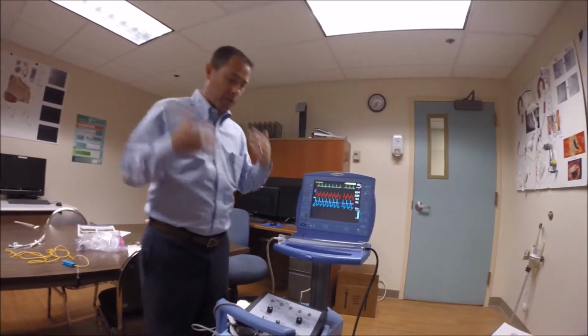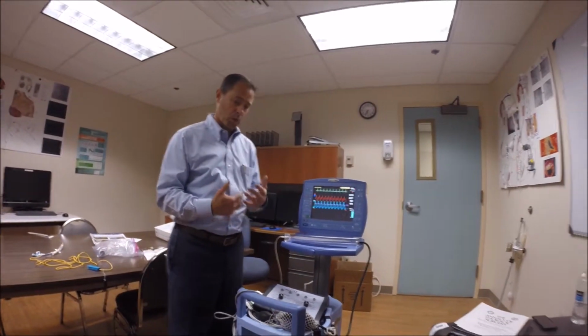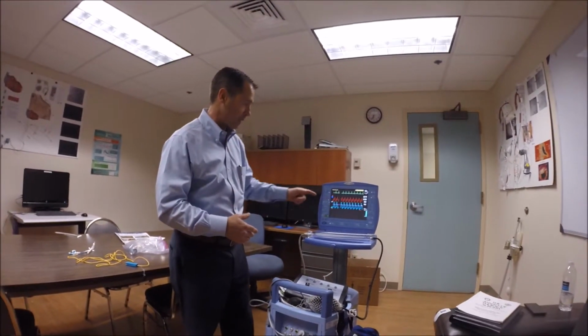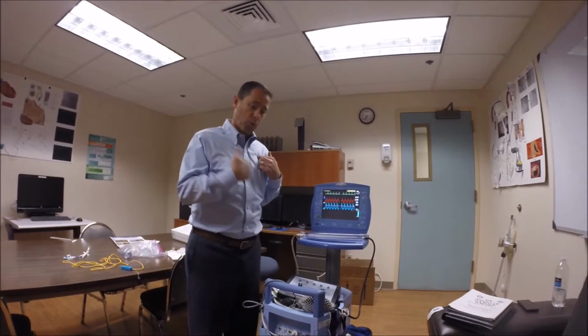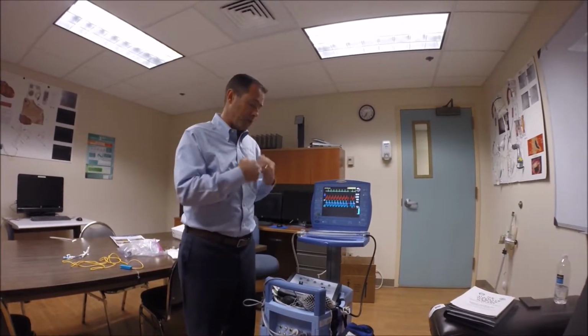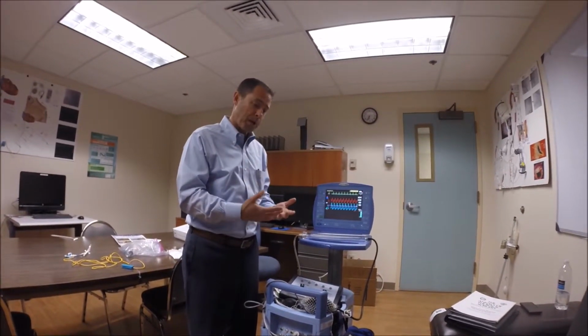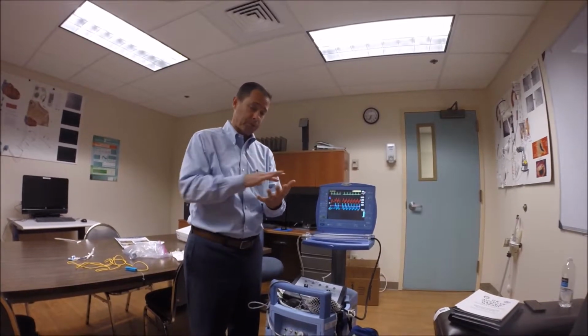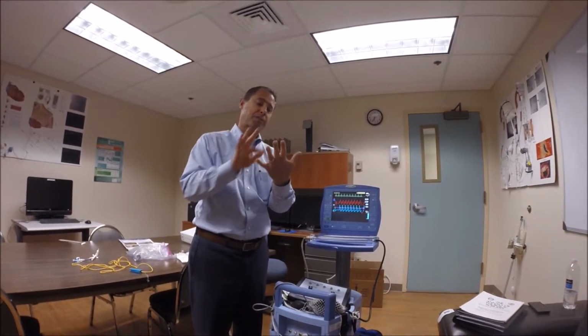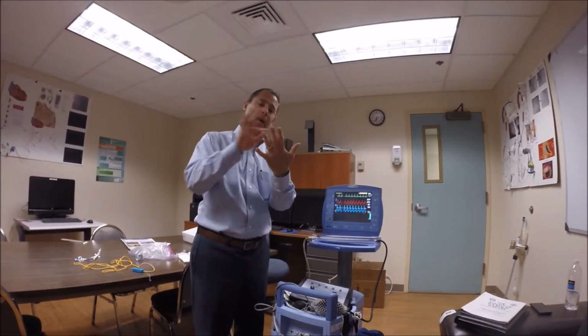In the background of the pump there's best signal analysis, meaning it's always capturing the right ECG. If you lose a lead off the patient without the pump stopping or interrupting therapy, it instantly jumps to the next best lead, it doesn't have to circle back around.